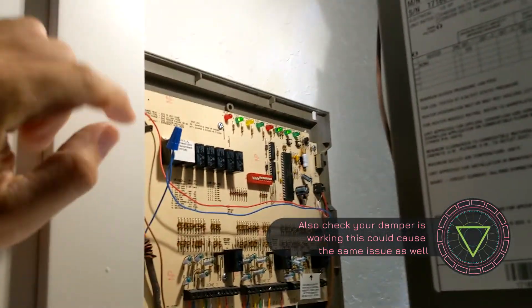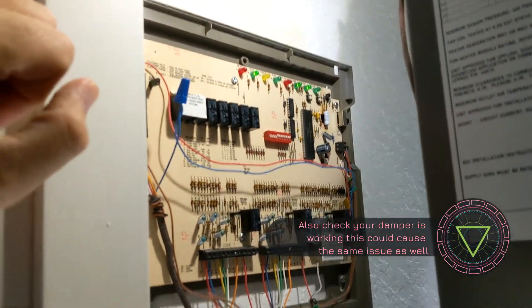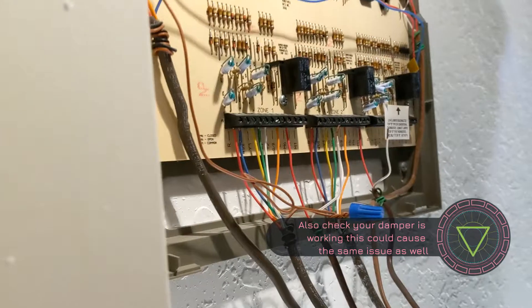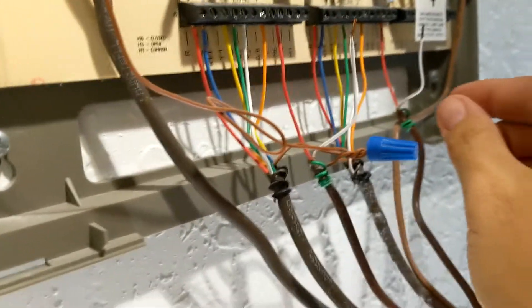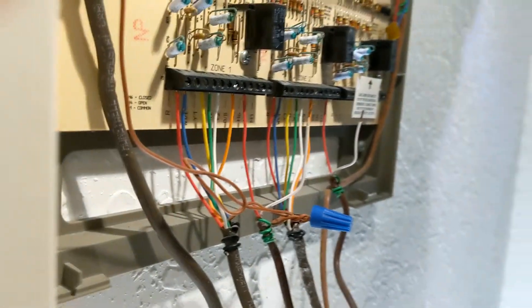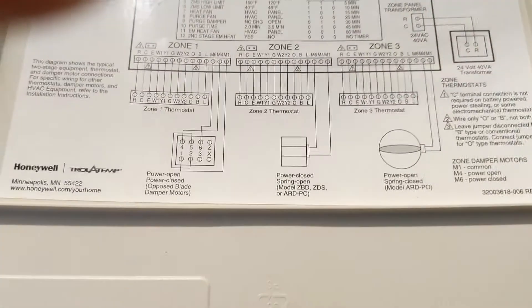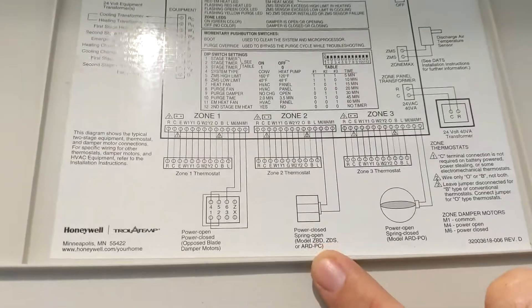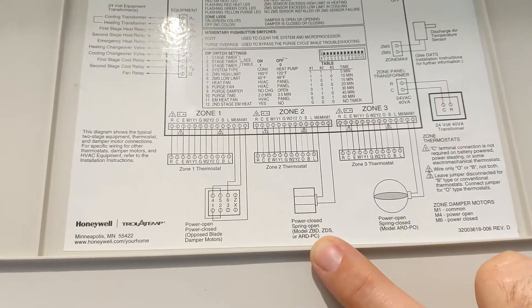But it would not open the dampers for zone two. So what I did to bypass this was go to zone two and disconnect the power to the damper.